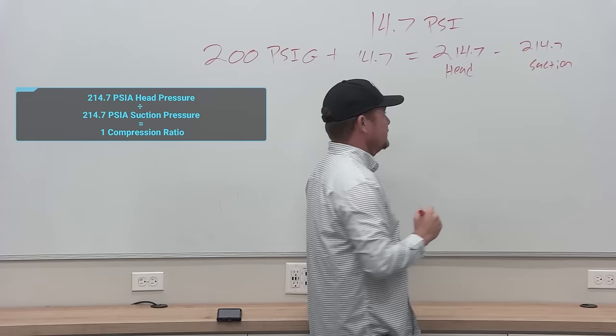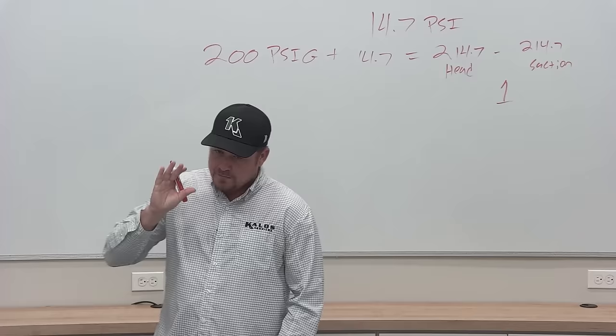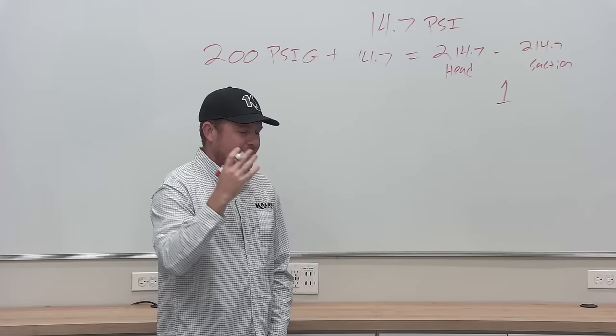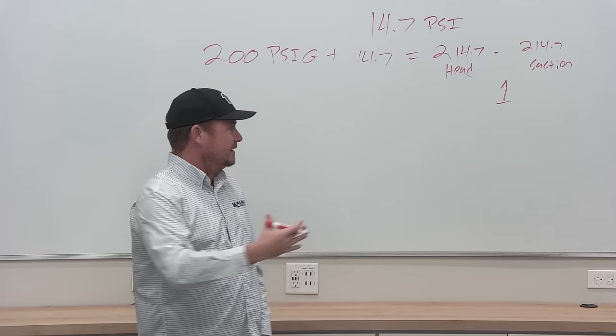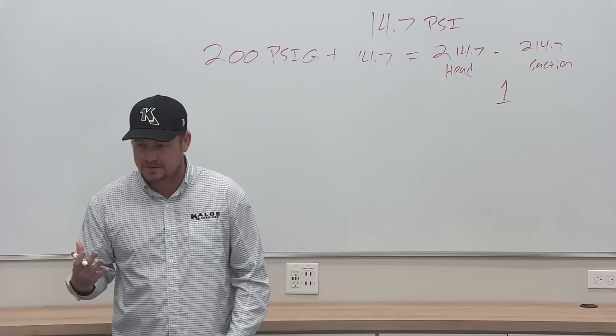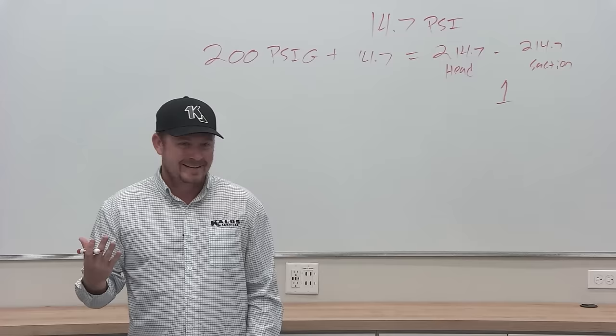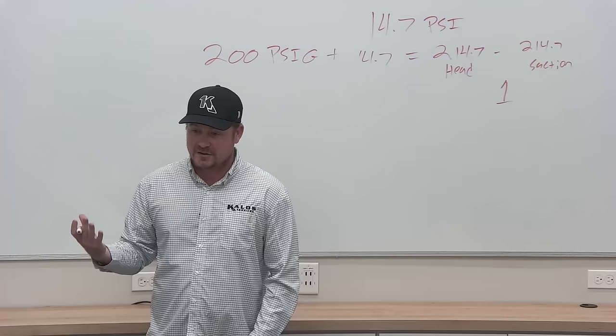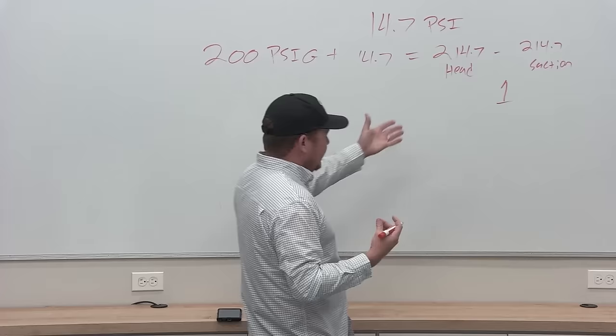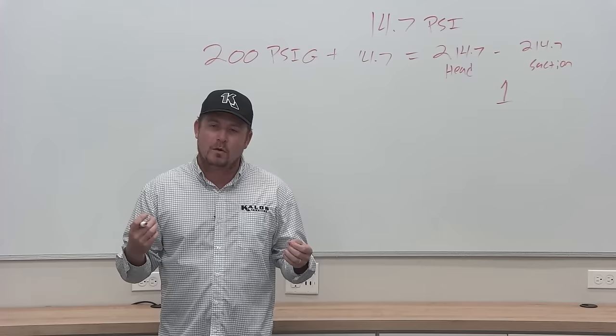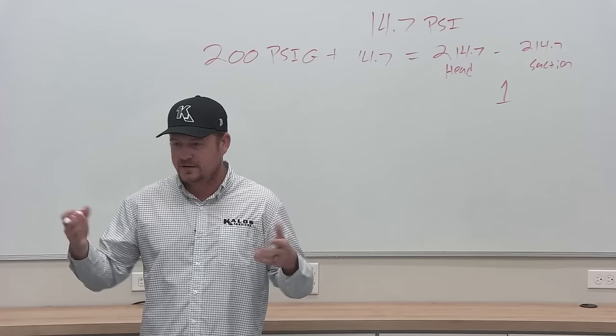I like to do this right off the bat because when we talk about compression ratio in engineering, people often say lower compression ratio is better — lower compression ratio equals better efficiency. Well, obviously we have a problem, because if the system is not running at all, how efficient is it? It's consuming no power but also producing no cooling or heating. So it's not really efficient even though it has a low compression ratio. In fact, there was actually a fault on one brand that would say 'low compression ratio' when essentially the compressor wasn't pumping at all.